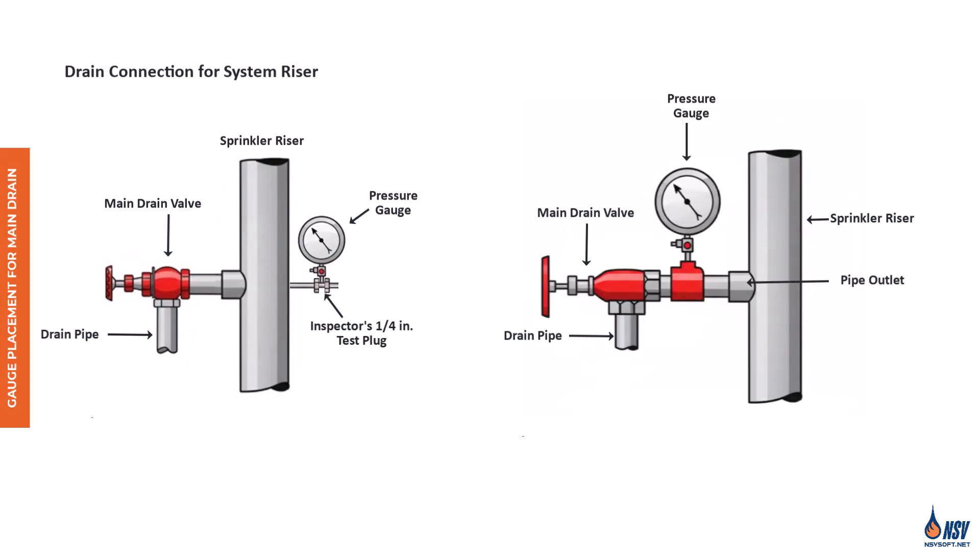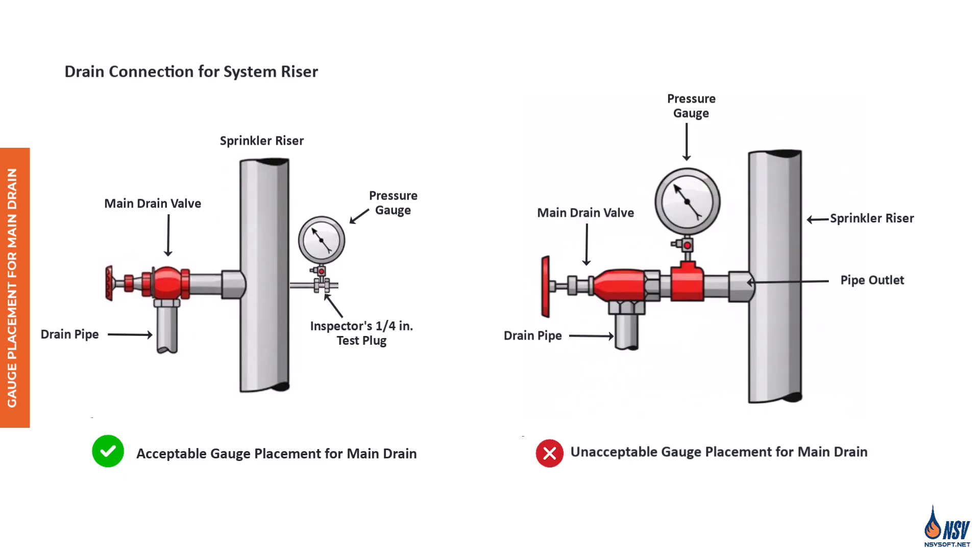It is worth mentioning an important point here. The main drain test is a critical procedure for verifying water supply conditions in a sprinkler system. The main drain test consists of reading the pressure in the system before opening the drain, after opening the main drain fully, and then after closing the drain. However, the test cannot be performed without a gauge. The location of the gauge in relation to the main drain is equally important because accurate readings depend on proper placement. For example, the figure on the left illustrates an acceptable installation where the gauge can measure pressure correctly. In contrast, the figure on the right shows an unacceptable arrangement where turbulence caused by a change in water flow direction leads to incorrect gauge readings.